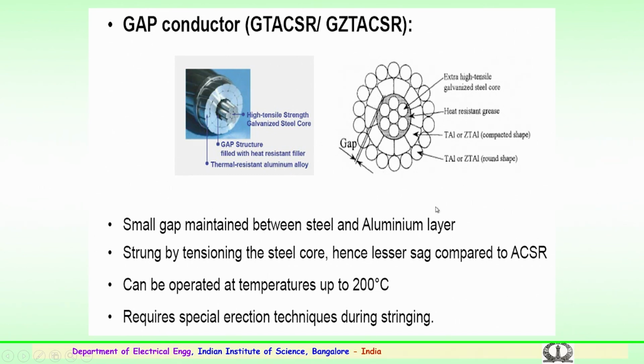So, there is the thermal resistant aluminum alloy, and the small gap between them is a heat resistant filler, which is maintained between the steel and aluminum. Here basically this junction is the gap, and these conductors are strung by tensioning the steel core. So, hence these have a lesser sag, again in comparison to the aluminum conductor steel reinforced type.